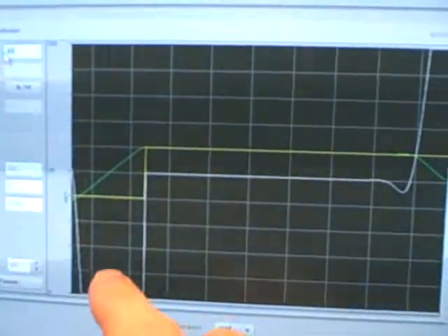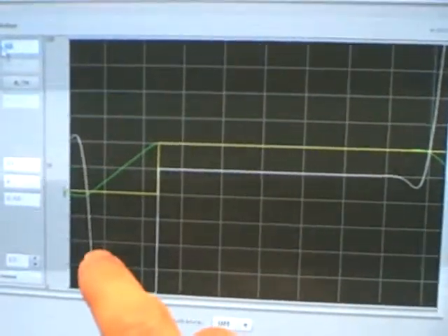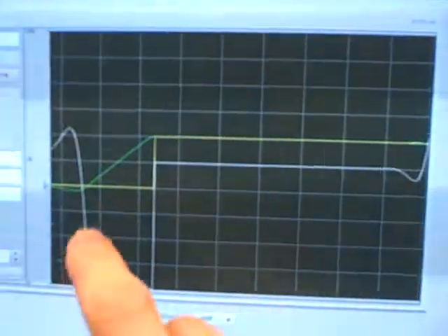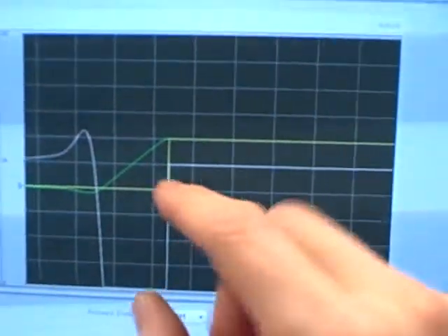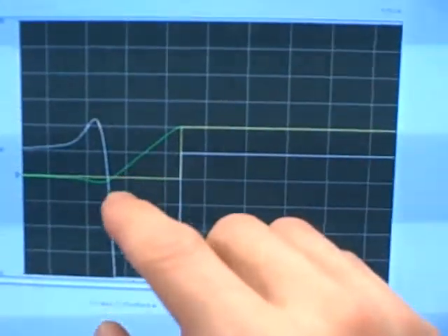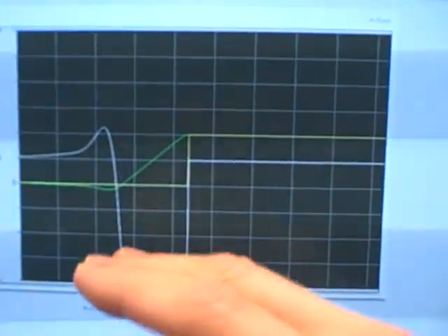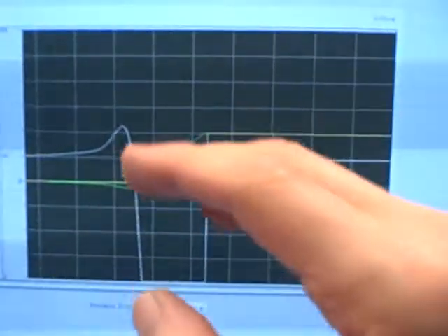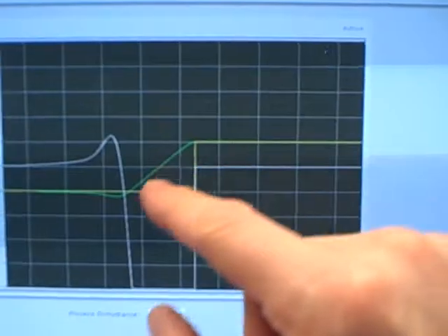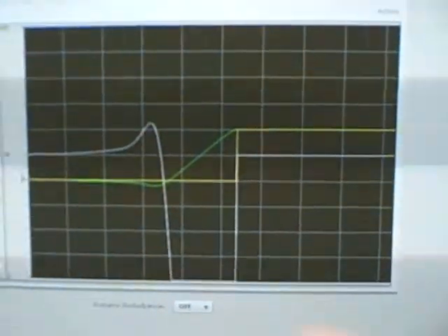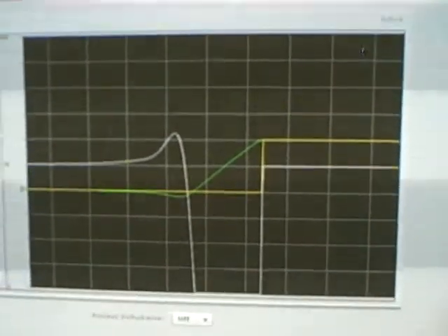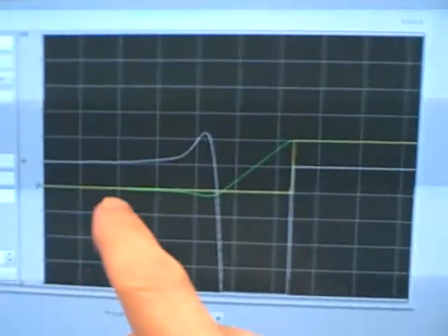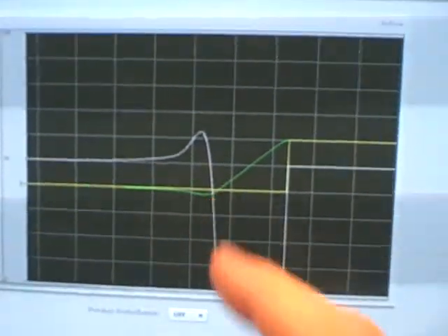When we reach set point, it takes a little bit before the valve opens back up, and when it does, it overshoots and then comes back down, because during this time when the process variable was over the set point, integral action was winding down, and it was basically taking the bias value of the controller and reducing it. That meant that we actually undershot the set point, which meant that proportional action had to pick us up, and integral action too, and start to wind the valve output back up. And so in other words, we end up with this undershoot after a set point change precisely because we have integral action here. This is a phenomenon you're going to see in any integrating process. If you put integral controller action on an integrating process, you guarantee overshoot or undershoot on set point changes.